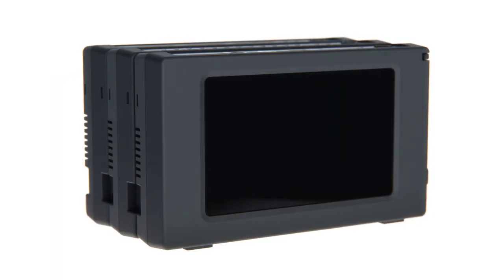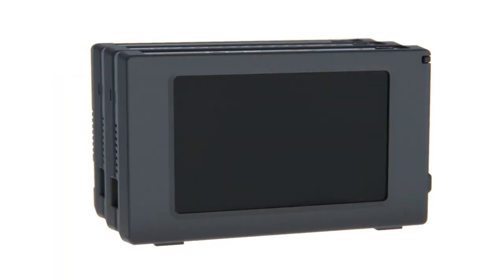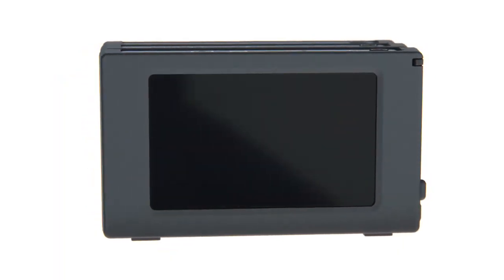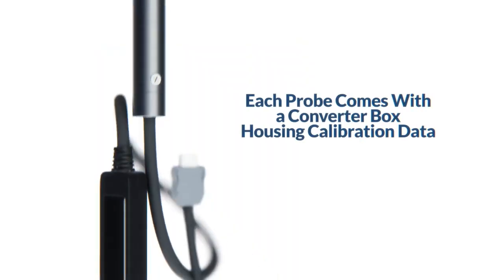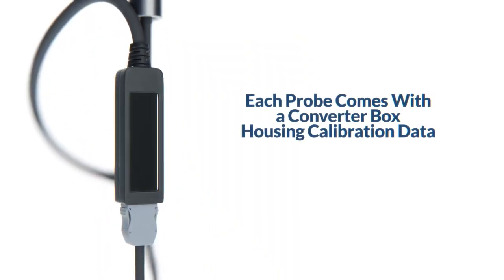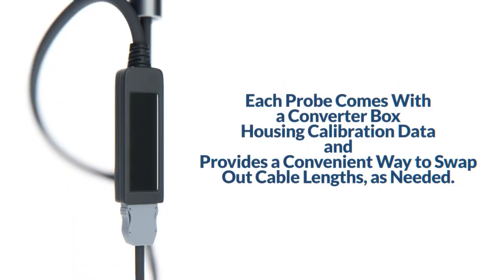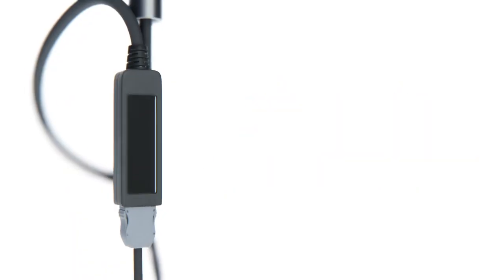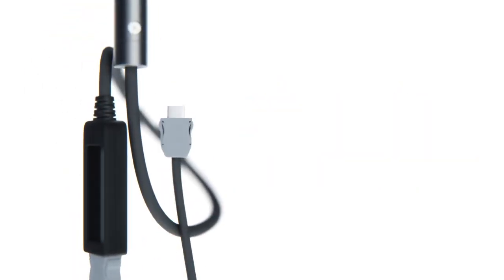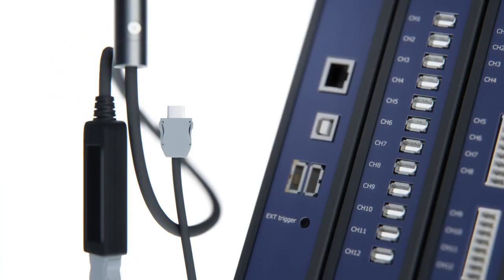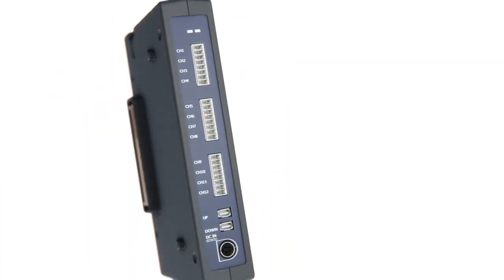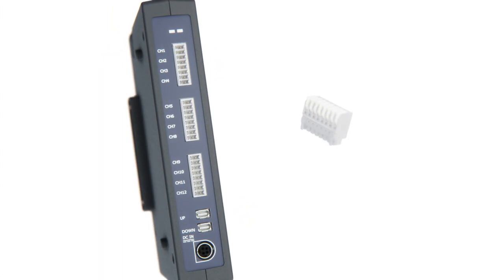After power sources have been connected, keep the power off for the time being. The next step is to begin connecting probes. Each probe comes with a converter box that houses its calibration data and provides a convenient way to swap out different lengths of cable as needed. Once a probe connection cable has been attached, you can connect to any of the probe terminals on the hub unit. When using an analog unit for measurement data conversion, you'll need to use the dividing block.